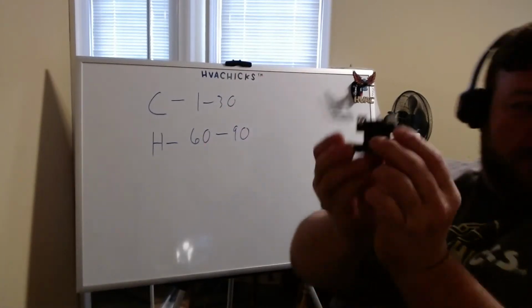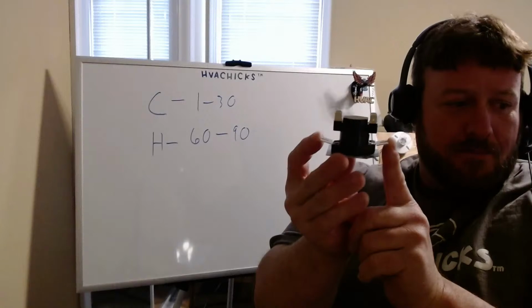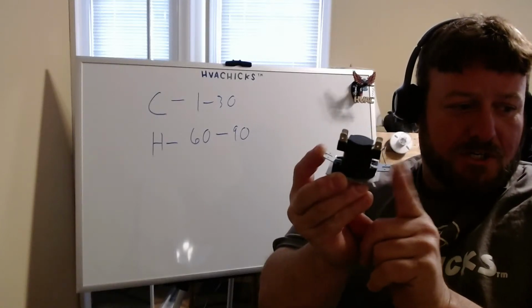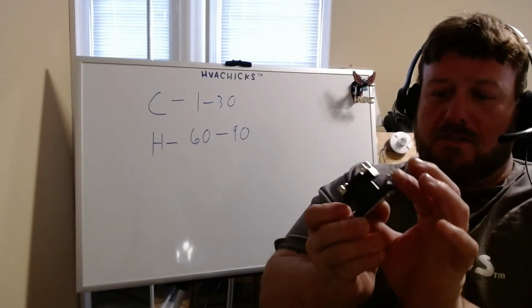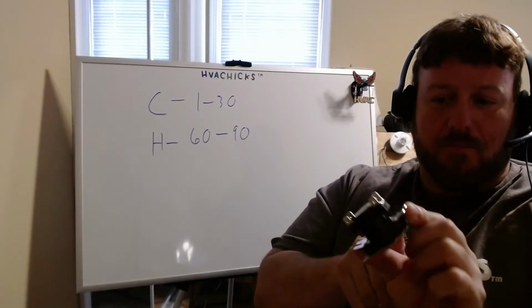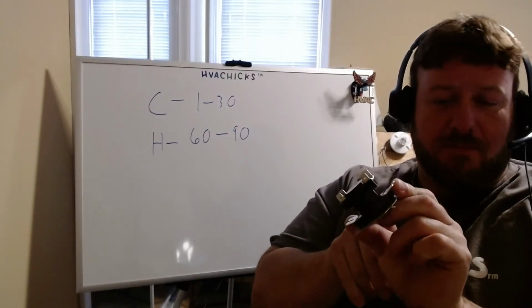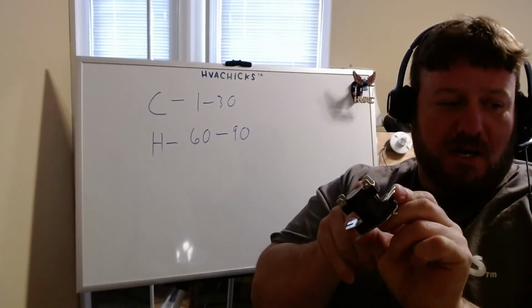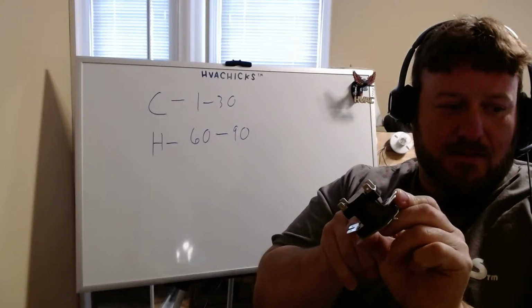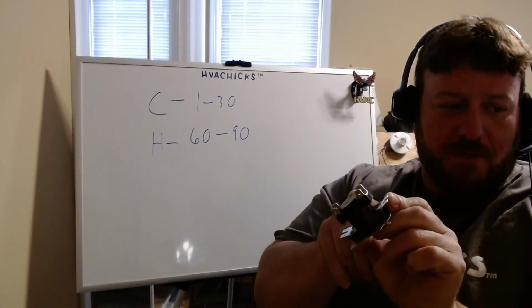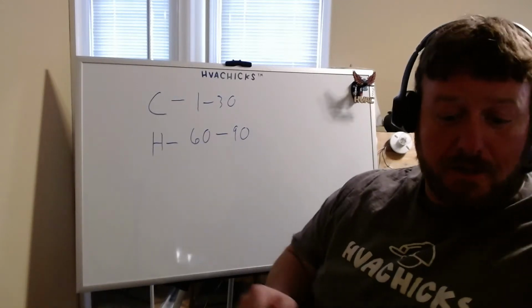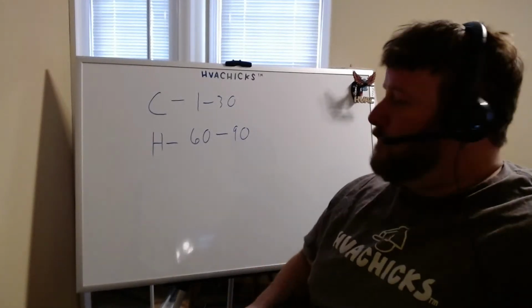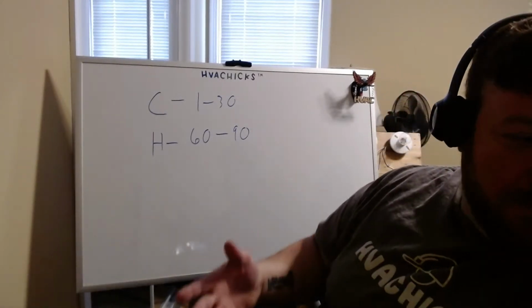So when 24 volts is applied to your bottom, when this gets energized, inside of here is a bimetal disc and a pin. When that pin heats up, the disc heats up, it pushes a pin, which in turn makes this have contact. Little porcelain pin, boom, makes contact. This porcelain's not energized, doesn't create electricity. So when it does that, it has to heat up for a certain time.